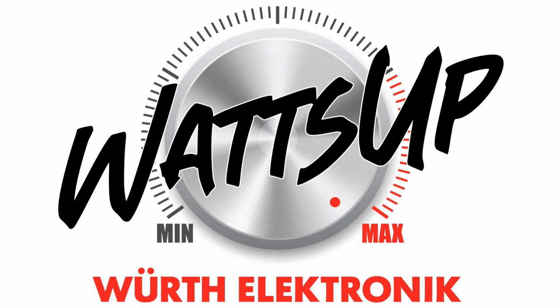Here, one point is also very important: you are comparing a system accuracy versus a device accuracy. System accuracy means that you have the RTD, your analog filters, and then your ADC, and this whole accuracy is called the whole system accuracy. On the other hand, the sensor, being one single IC, comes fully pre-calibrated. In the same way, you sometimes have to perform, as mentioned, the whole system's calibration. For that, the whole system needs to be kept at one single temperature. This could be tricky in some of the applications.